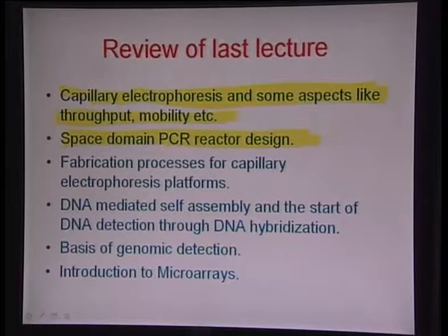In the space domain devices, you physically oscillate this PCR fluid as a micro droplet over the 3 different heating zones, and this helps you avoid the additional ramp up and ramp down time that the time domain device would require.